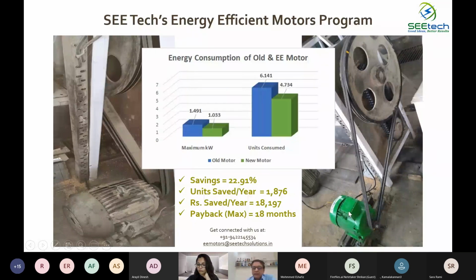Now the synchronous RPM - those from an electrical engineering background will understand that the RPM of this motor is 1450, whereas the RPM of this motor is 1500. If you install a VFD drive here, the cost of the drive becomes very high. So what you have to do is accordingly change the pulley size. Both pulleys were changed, because at the end of the day, whatever motor you put, your shaft must operate at the same speed so the production requirement doesn't change.